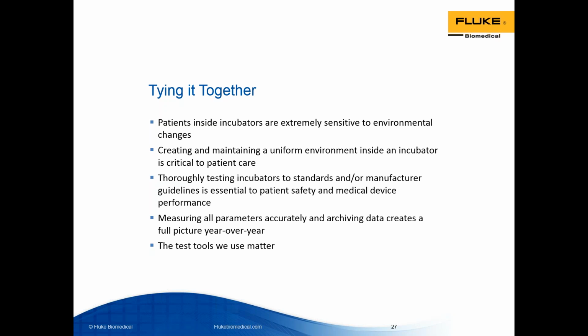So if I get a call from a nurse and they say, oh, this incubator isn't working. Okay, great. I run up there and do a quick check. Nothing seems to be wrong. They tell me again the incubator's not working. Well, the patients are in there for long term, right? More than just a few minutes, sometimes up to months at a time. So what's going on at hour 3? What's going on at hour 4? How do you do the long-term testing? And how do you know if something's going on with temperature? How do you know that that's not caused by airflow and thus, the air fan, things like that? So measuring all parameters simultaneously will help give you that big picture.